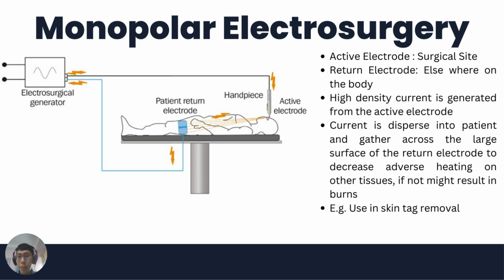The circuit from the active electrode to the patient return electrode is completed when an electric current flows through the patient. The role of the patient return electrode is to safely extract current from the patient. Preferably, the current is dispersed into the patient and gathered across the large surface of the return electrode to decrease the adverse heating on non-target tissue. If the heat generated over time is not properly dispersed, a return electrode burn may occur. An example for such usage is skin tag removal.